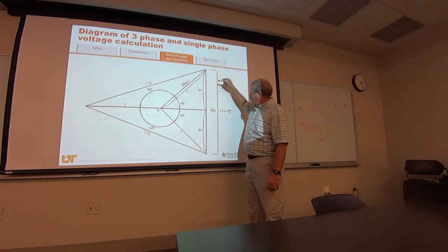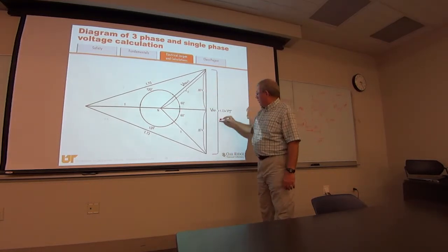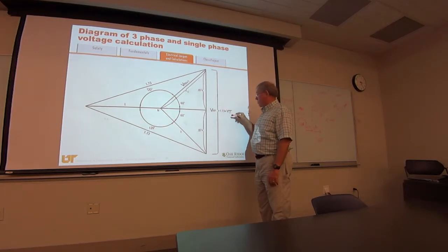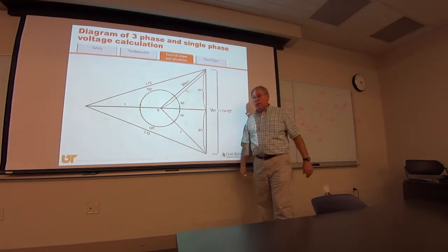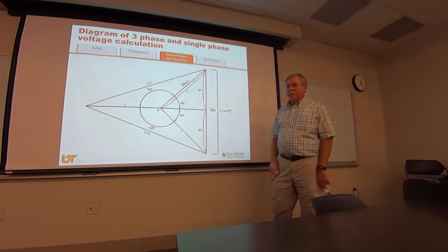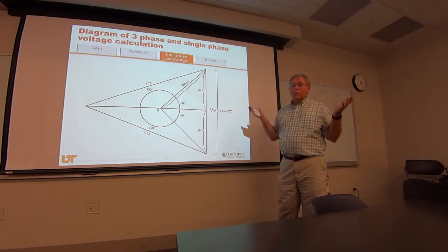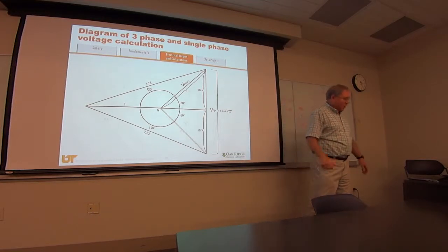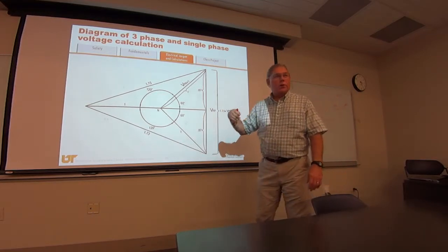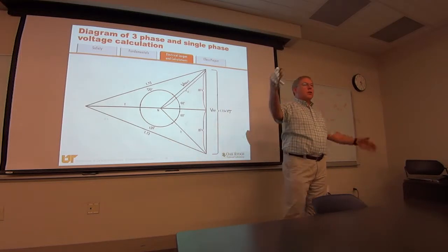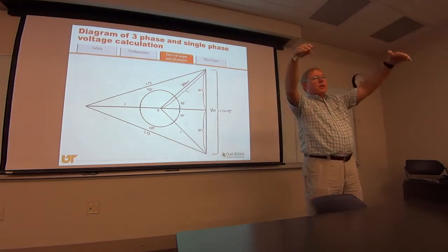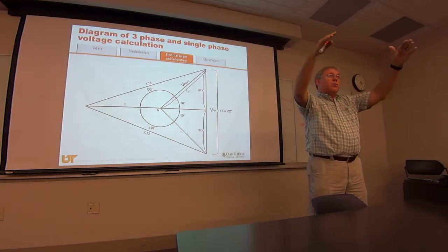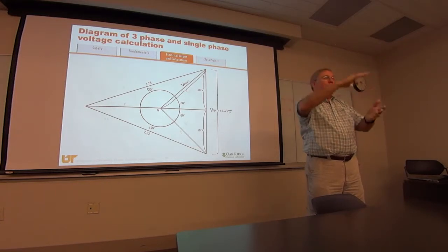So the voltage phase to phase is the sum of that, which is 1.73, which is the square root of 3. If you do your trig identities, that's what you'll find out. It's very simple. I mean, it's no big secret. I just spilled the beans. Y'all know now all about electrical engineering. I'm sorry. So when you've got three-phase voltage, delta voltage, phase-to-phase voltage is a higher number, phase to neutral is a lower number, and the difference is a 1.73 multiplier.